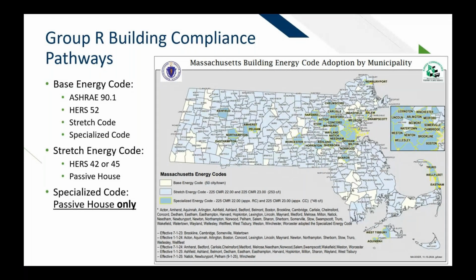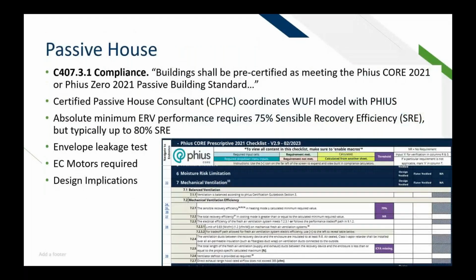We're gonna keep going. So what is passive house? Passive house is a compliance pathway, like I said, where your building should be pre-certified as meeting the prescriptive checklist of PHIUS Core or PHIUS Zero. In order to do that, you've got to work with a certified passive house consultant, or a CPHC, like I just mentioned, who will coordinate a WUFI model, which is your energy model, with PHIUS. Within that model, there are some absolutes, and one of those is that your ERV performance will absolutely require a minimum of 75% sensible recovery efficiency, or SRE. Now, that said, that's kind of like the bottom barrel. Typically you'll end up with about an 80% SRE requirement from the ERV.